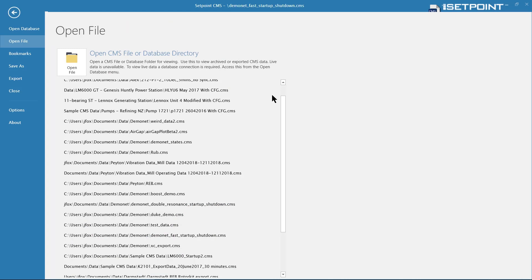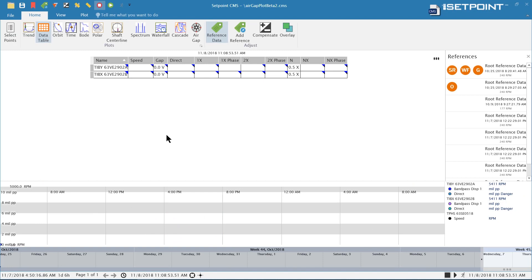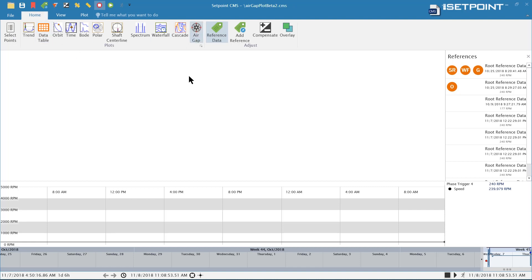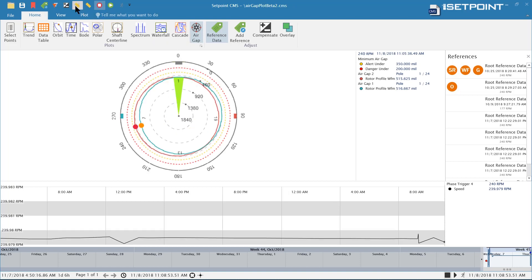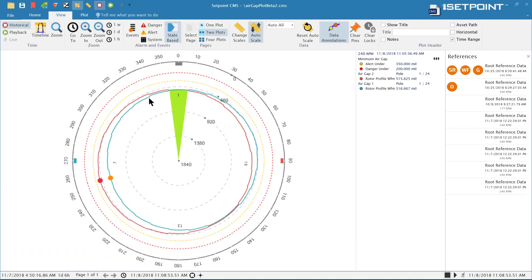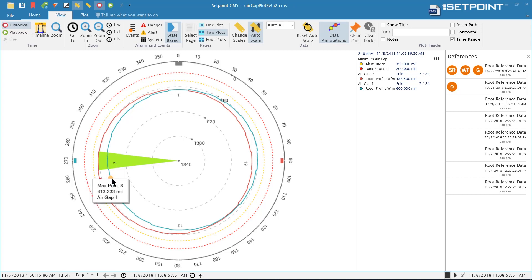The final feature we want to look at today is an air gap plot. We've added a hydro-specific plot so you can see the air gap around the hydro turbine. Let me open up that file and bring up the plot. Here we can see the air gap plot. Each of the air gap sensors will show up on this plot and we also show the setpoint values so you can see how close we're getting to the alarm on it. These outer circles here, the red and yellow ones, are the alert and danger limits, so you can see that as the air gap approaches our clearance in the turbine.